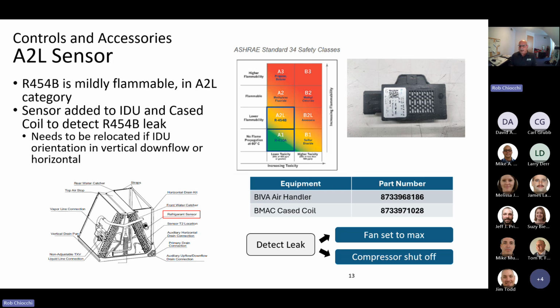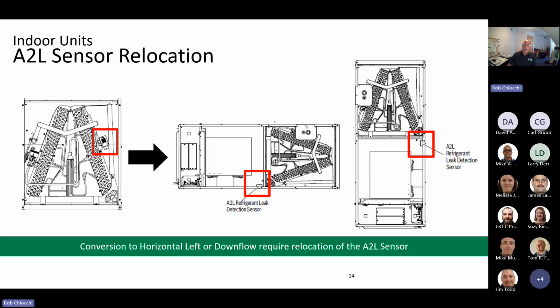One thing that all dealers will have to be aware of is if you change the orientation of the coil from upflow to either horizontal left, horizontal right, or downflow, the sensor will have to be moved, and there are very distinct instructions included with the equipment to show the location of where that sensor will need to go. Obviously, the sensor will most likely be located at the lowest point of the coil or the air handler, depending on the orientation, because the refrigerant is heavier than air, and we want that sensor at the lowest point. This is something that will have to be done.